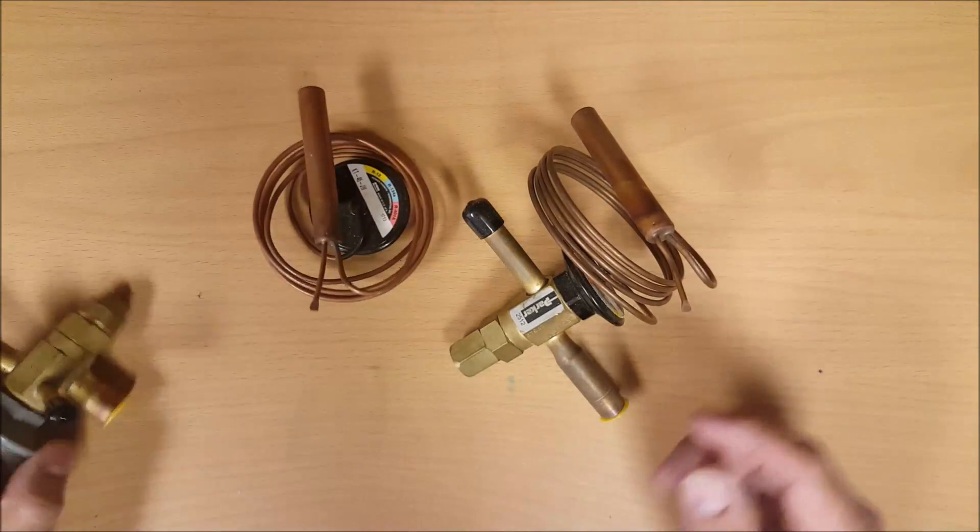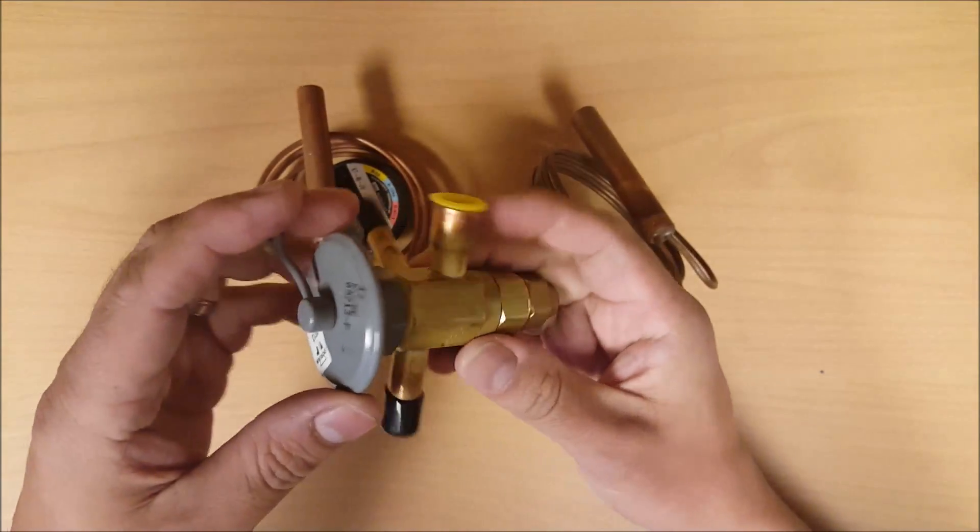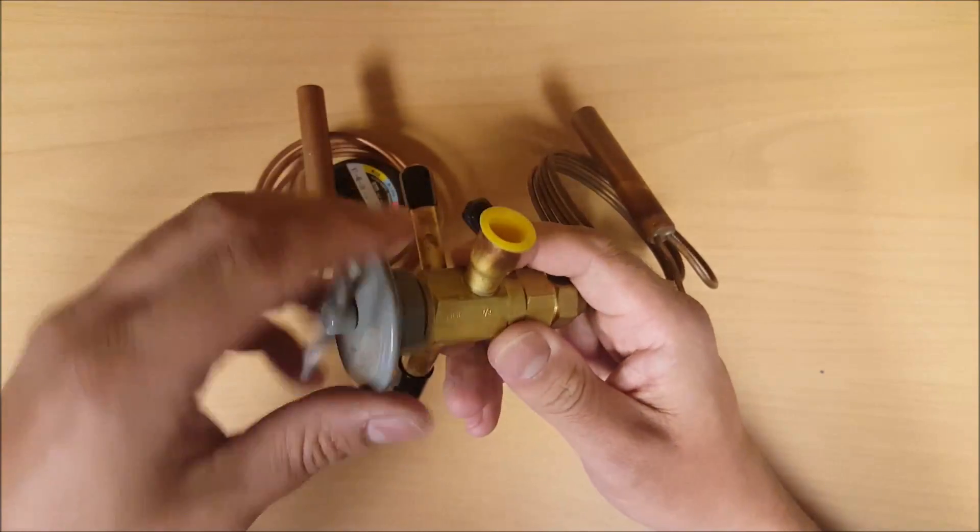Alright, next we're going to be looking at our expansion valves. Basically here's a sample expansion valve that we have. This one has a removable power element. These power elements can be swapped out. You can take this one off and pop a new one on. The reason you would want to do that is if you're changing refrigerant types.